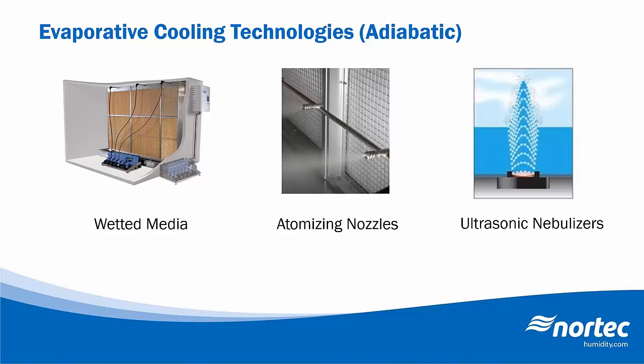The second type of system is an atomizing nozzle system. This type of system atomizes water into small droplets, typically around 10 to 15 microns in size. These droplets are created by pressurizing the water to roughly 1,000 psi and spraying those water droplets directly into the airstream using a nozzle array. The last technology that we'll look at here today is ultrasonic nebulizers. This type of system uses a series of piezoelectric transducers to effectively break the surface tension of the water to produce a fine mist. The droplet size with this type of system is typically around 1 to 5 microns in size.